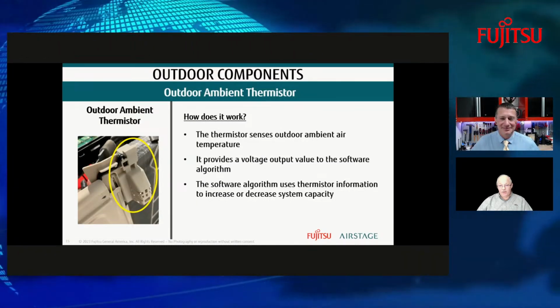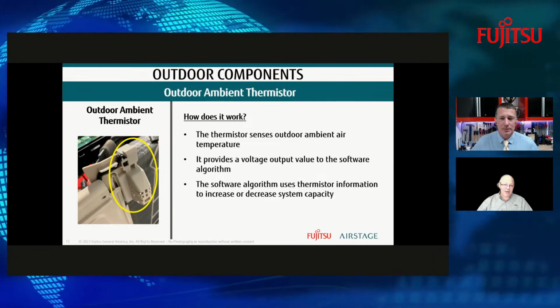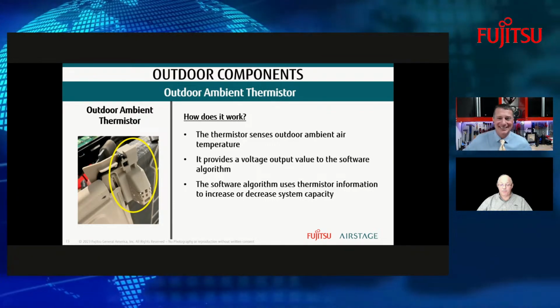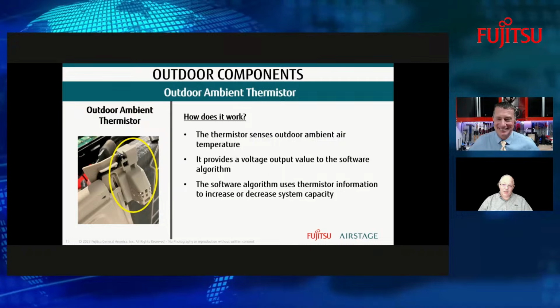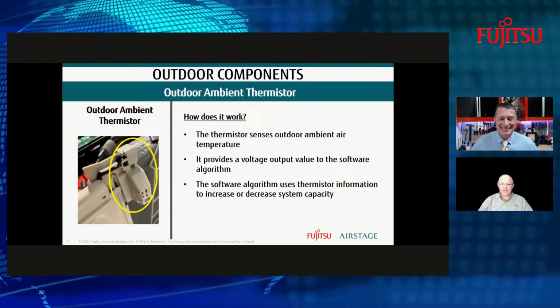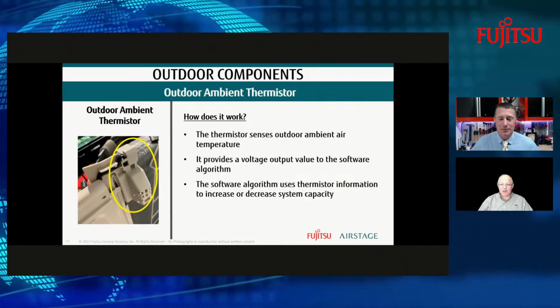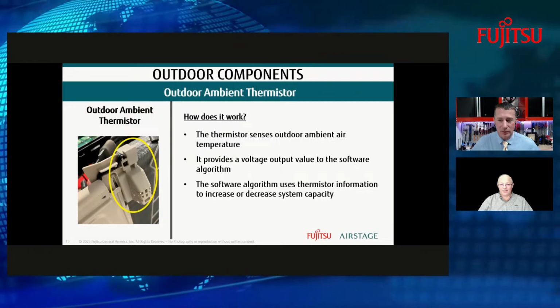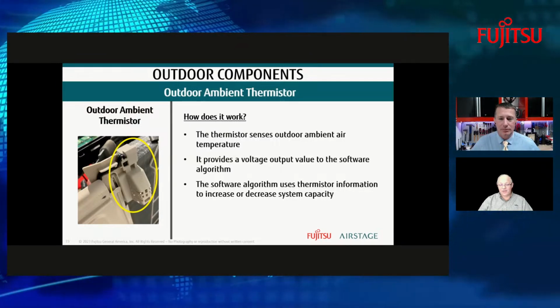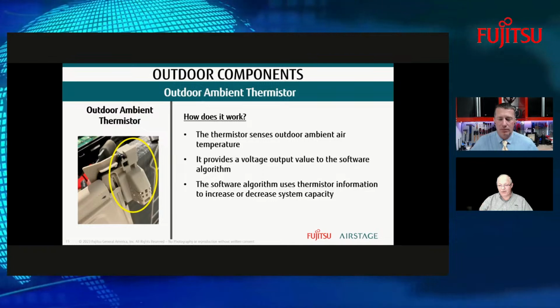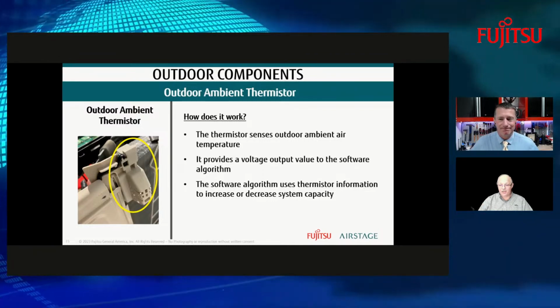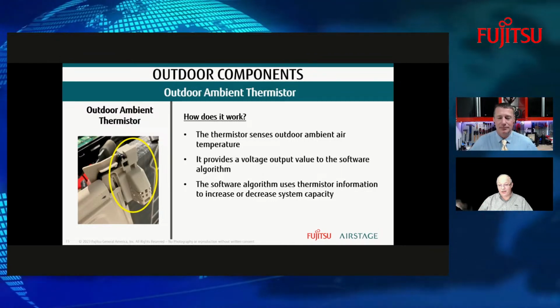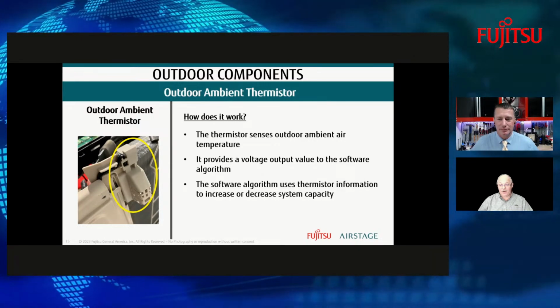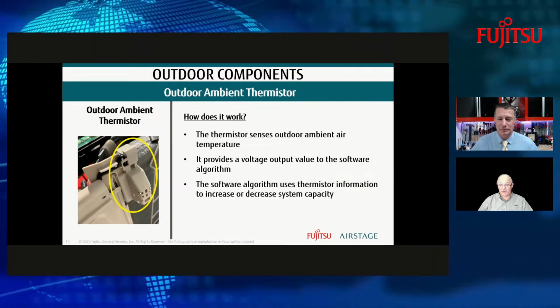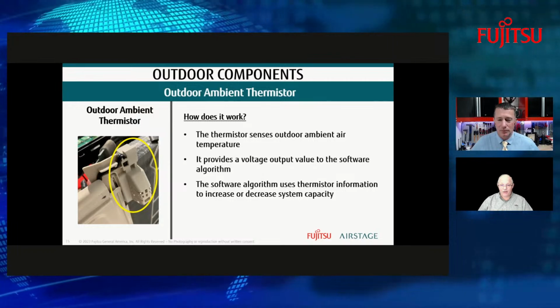Now we've got the outdoor ambient thermistor. Man, you guys have so many thermistors. What are we reading? Well, that's how the system knows exactly how much capacity it's going to run at. If you take a single speed heat pump, it doesn't know anything. It just knows that the thermostat inside said, you set me at 75 and the temperature went to 77 or 78, I need to turn on.